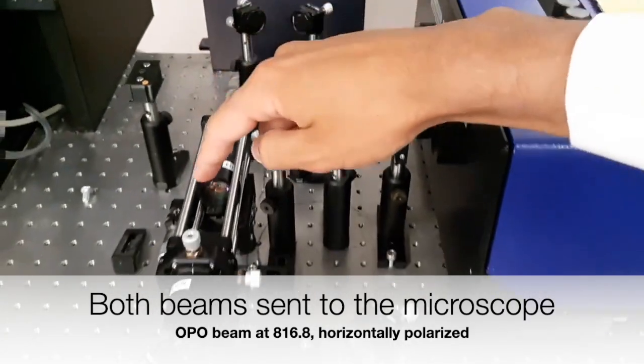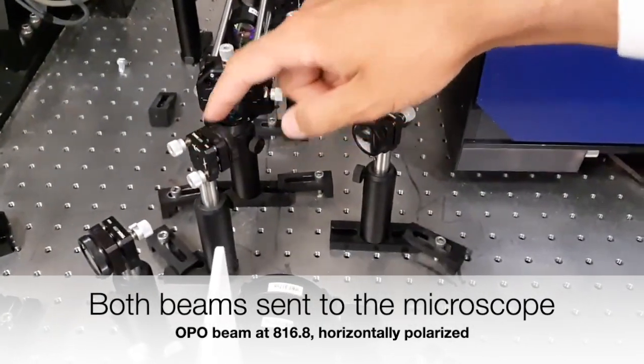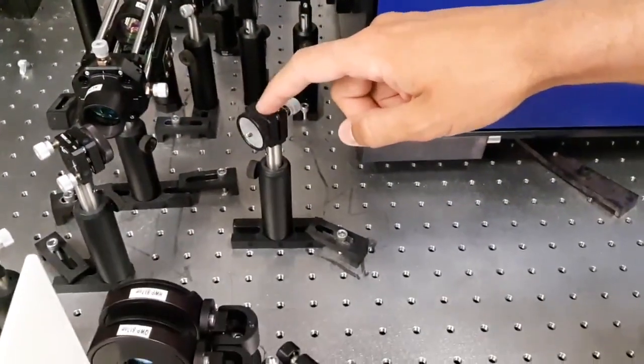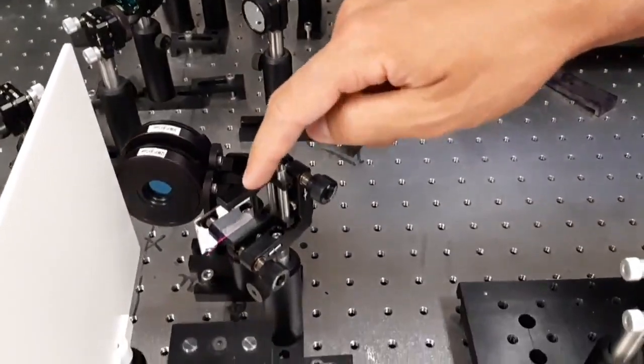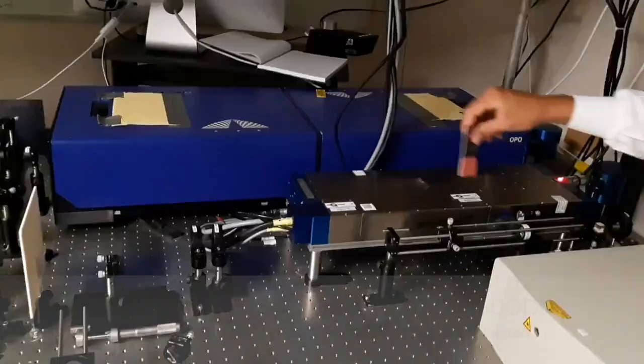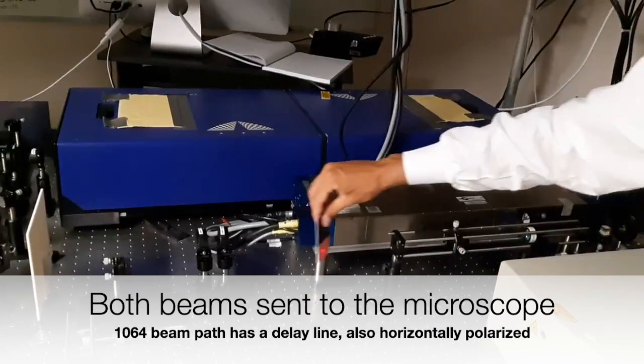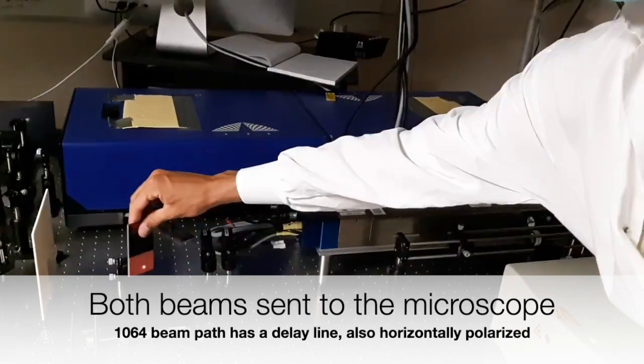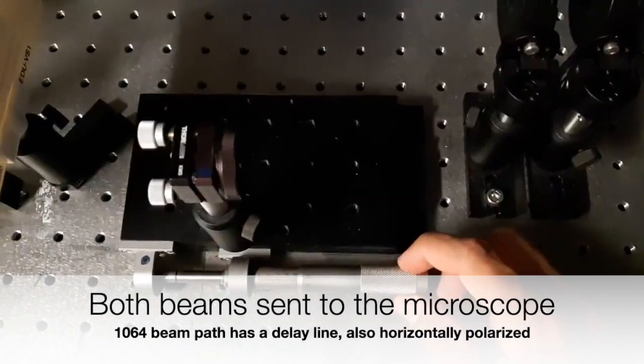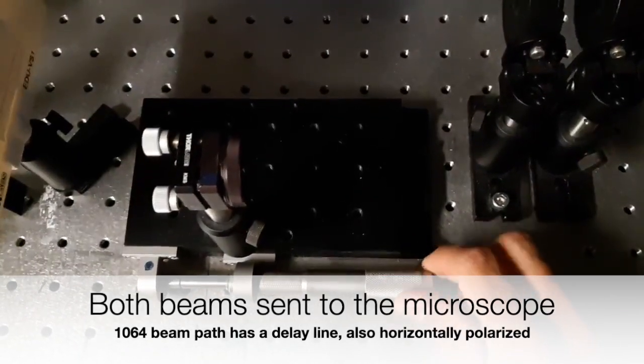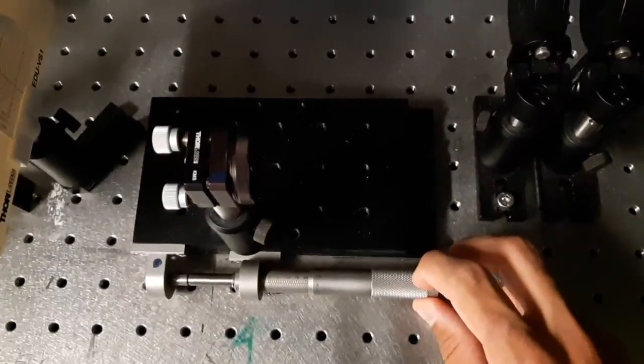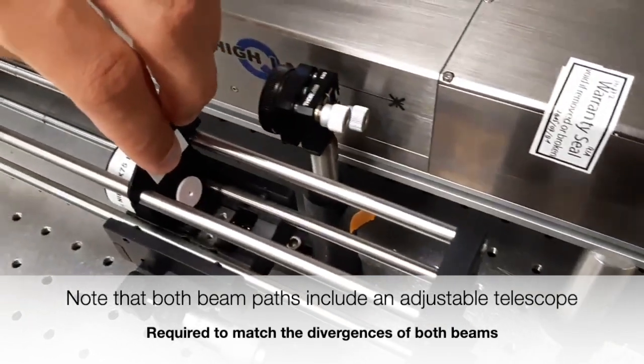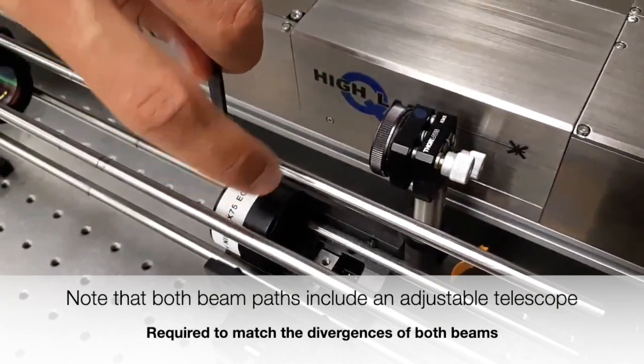The OPO beam goes through its own beam path with a 1-to-1 telescope adjustable for divergence and ends at a reflective dichroic mirror that will send it to the microscope. On the other hand, the 1064 beam path has a delay line, which we will use to overlap the pulses temporally, and also an adjustable 1-to-1 telescope to modify the divergence if needed.